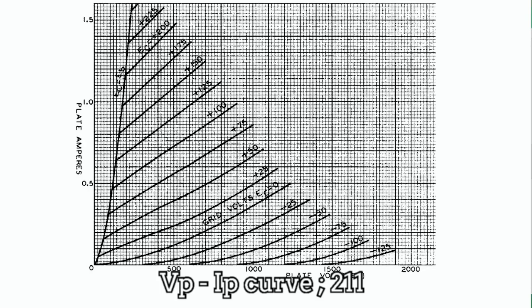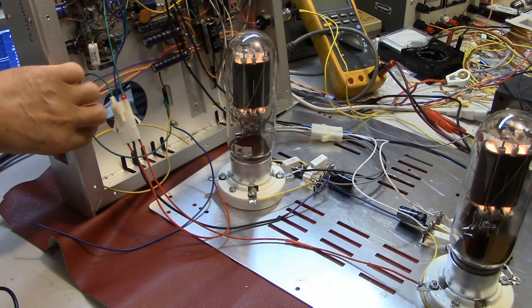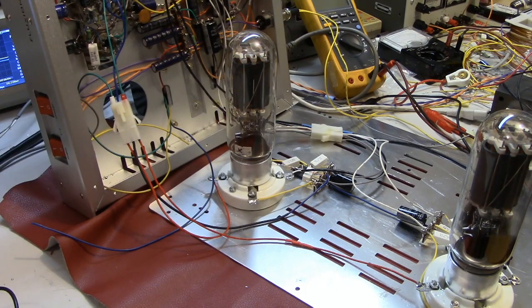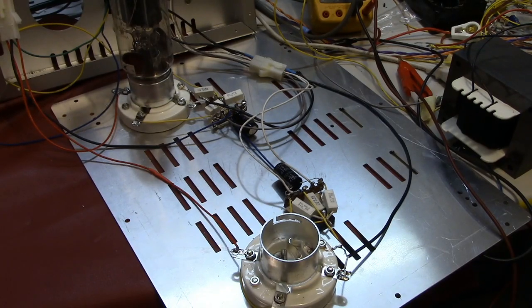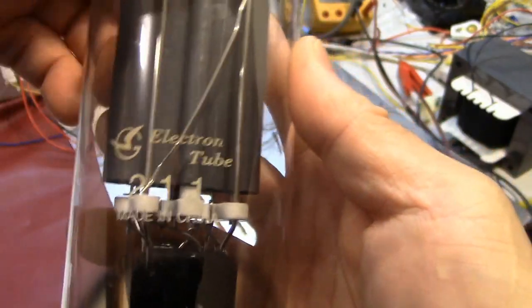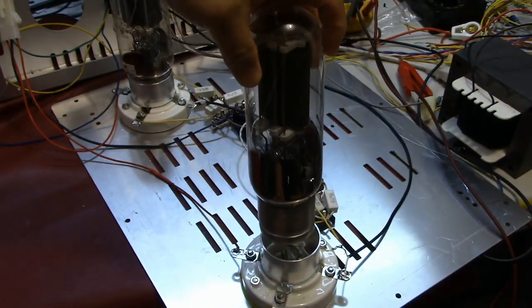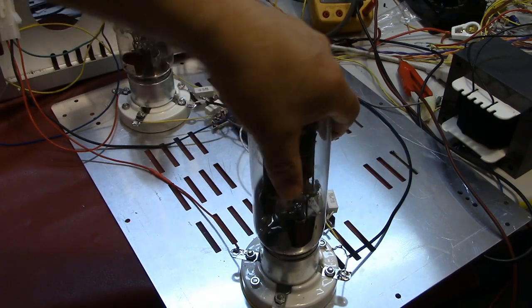So what about 211? As shown in the graph, if you apply 15 volts to the grid and 500 volts to the plate, the current is 200 milliamps. Plate dissipation at this time is 100 watts. Therefore, this will exceed the maximum rating.